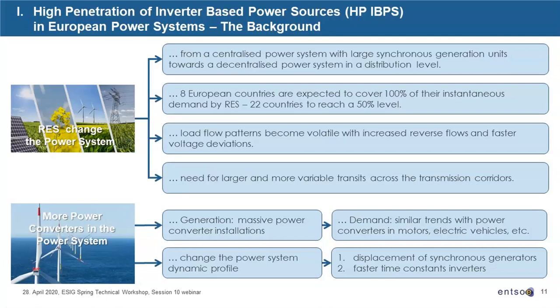A number of European countries are very soon expecting to reach 100% instantaneous penetration of RES generation. Quite a large number more will be at the 50% level. Load flow patterns will change a lot, and we will experience more and more larger and variable power transits across the transmission corridors, because the RES power sources are mainly located remotely. In particular, together with the ambitions of the Green Deal, we move towards offshore wind generation, since onshore acceptability is limited and resources are limited. A large portion of the wind energy in the future shall come from offshore generators.